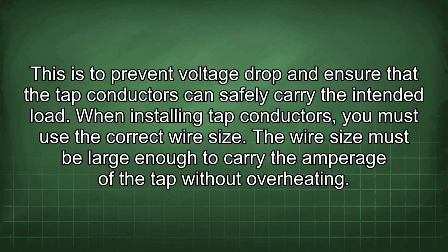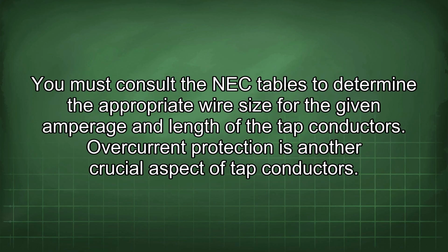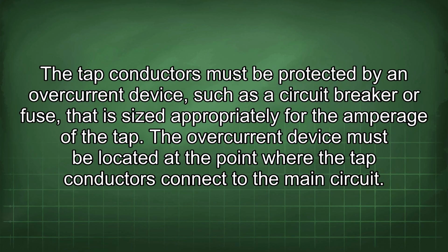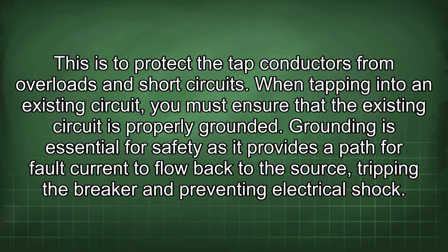When installing tap conductors, you must use the correct wire size. The wire size must be large enough to carry the amperage of the tap without overheating. You must consult the NEC tables to determine the appropriate wire size for the given amperage and length of the tap conductors. Overcurrent protection is another crucial aspect of tap conductors. The tap conductors must be protected by an overcurrent device, such as a circuit breaker or fuse, that is sized appropriately for the amperage of the tap. The overcurrent device must be located at the point where the tap conductors connect to the main circuit. This is to protect the tap conductors from overloads and short circuits.